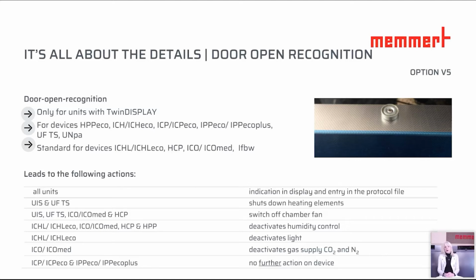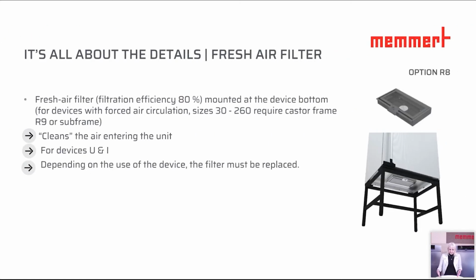We can even see on the display of the unit next to the temperature the indication when the door is open, so it's a small symbol. Otherwise, it is also an entry in the protocol file, so you will see that the door has been opened. And why is this important? This is important when we open the door. You all know there's influence on the interior condition, so that can drop temperatures, that can drop humidity. So all this is going to be recorded. Let's go on to the next one.